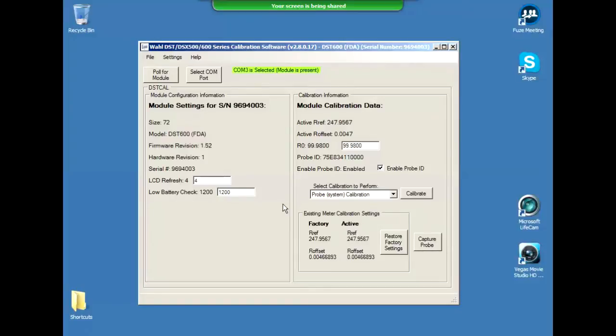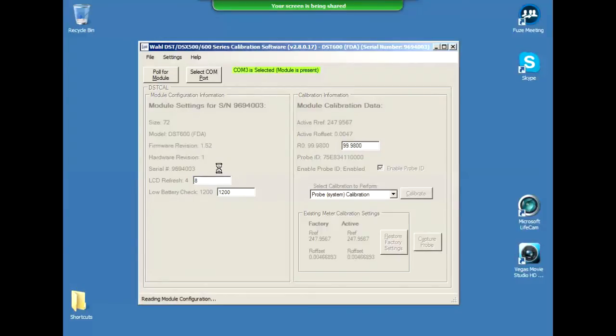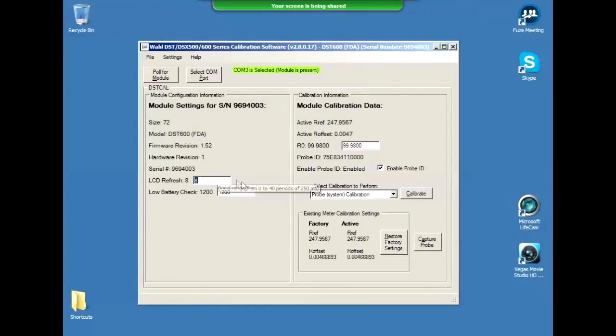If we're going to change anything, and I don't have a keyboard, but Megan does, so you can put 8 in there. And I think we ship these set at 8, I believe now. But you notice she already hit enter. But once you populate that, the set button came up, or you can hit enter. So that's set now at 2 seconds. Low battery check. Again, this is 250 milliseconds, so this is like every 5 minutes. And you don't really need to mess with that.